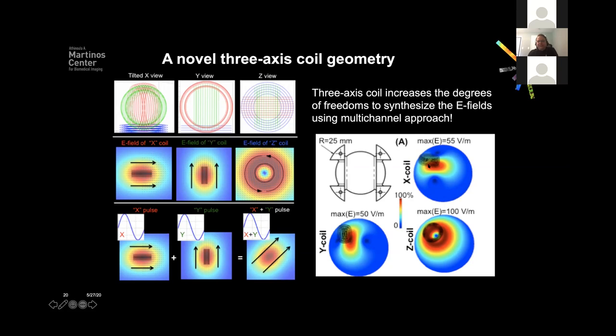Looking at the induced E-field patterns, there are pros and cons. The focality for the X and Y coils is better — they're inherently focal — but efficiency goes down by 50%. Nevertheless, we should think about what the whole array is capable of producing. Even though there's a hit in efficiency, we gain in packing density and the capability of adding more degrees of freedom.